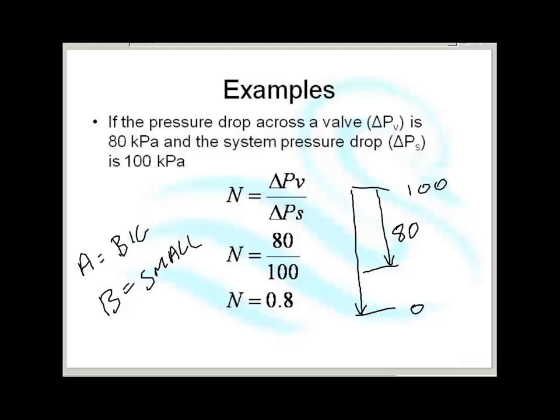Our perfect authority when you're buying a valve is 0.4, because that means it's just slightly too big. It's got a little bit in hand, and that's what we would be aiming for mostly. But given a choice between buying one that's slightly too big and slightly too small, we'll always go with slightly too big, because then if the flow is excessively throttled, it's not our fault.